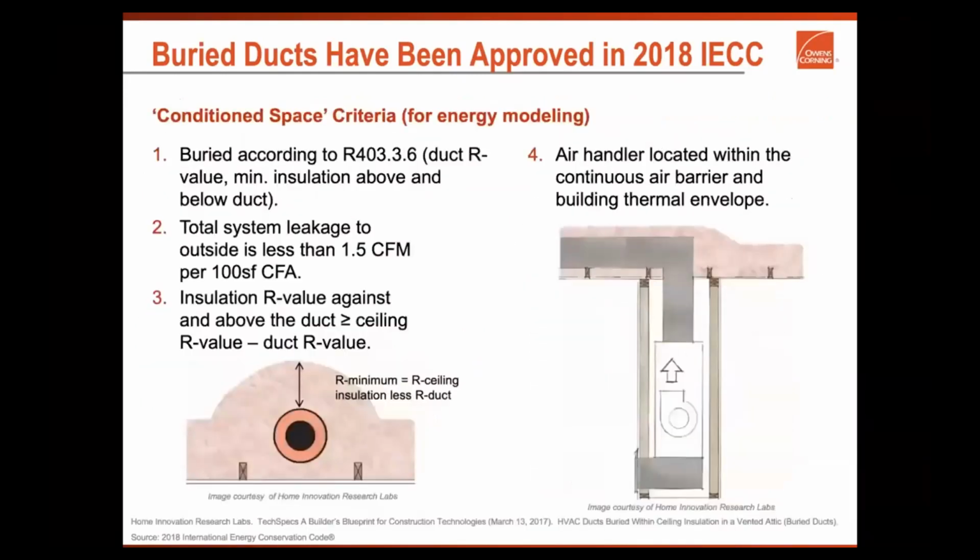So the conditioned space criteria, right? So for energy modeling, because technically these ducts are not in conditioned space at all. So the buried duct allows us to say, hey, the unit should be in conditioned space. There is code language that allows the unit not to be in a closet. It could be in the attic. But 1.5 CFM per 100 square feet of leakage to the outside is important, because that makes the effective leakage so minimal that it's acting as if it is in conditioned space.